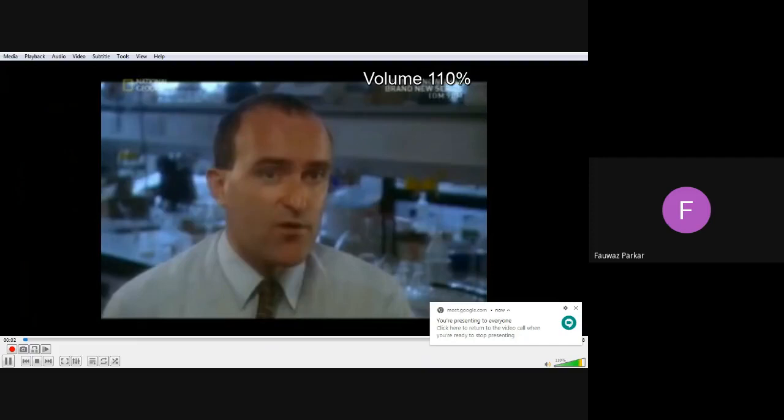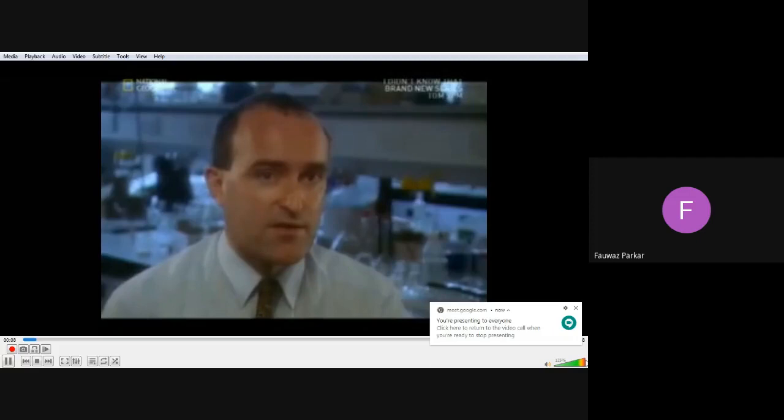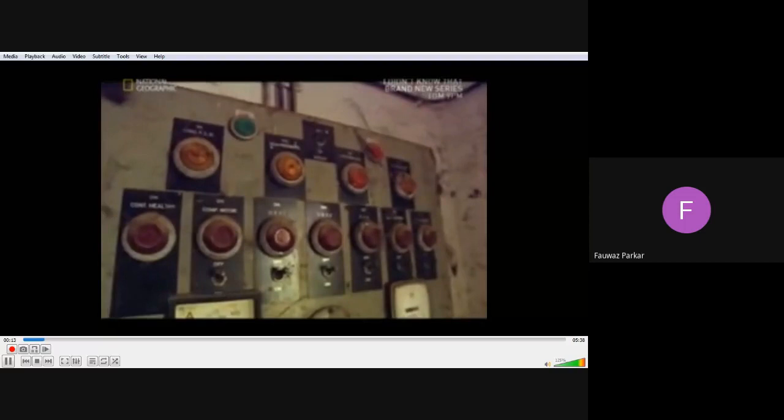...place when we're generating more heat than we can remove. The refrigeration system was there to remove heat. Switching it off made this incident much, much more likely. Incredibly, another safety device had been bypassed in defiance of Union Carbide's own operating instructions.